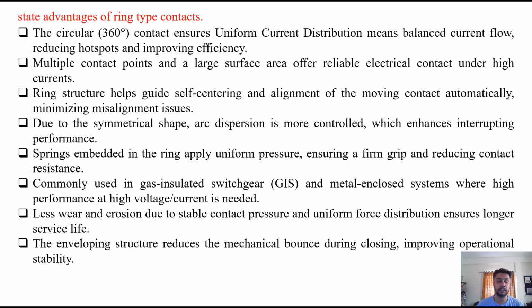Advantages of ring type contact. There are several advantages of this ring type contact. Some are listed here. The circular, that is 360 degree contact, ensures uniform current distribution, means balanced current flow, reducing hot spots and improving efficiency. Multiple contact points and a large surface area offer reliable electrical contact under high current, so it is suitable for very high current applications. Ring structures help guide self-centering and alignment of the moving contact automatically, so the misalignment issues are solved with the help of the ring type structure.